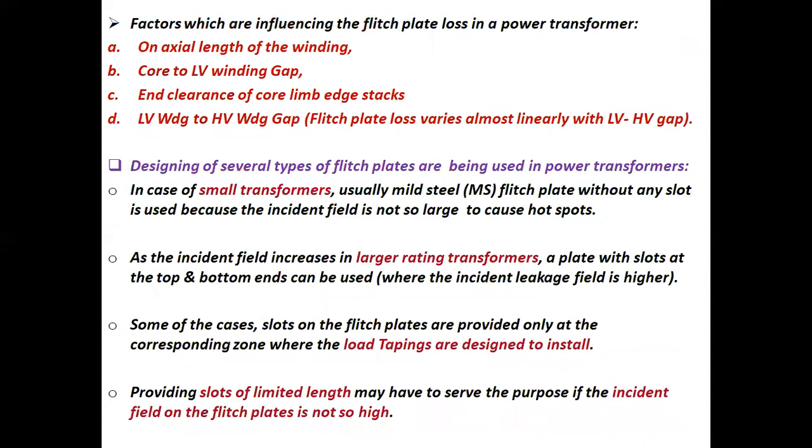Factors influencing the flitch plate loss in a power transformer: a. Axial length of winding. b. Core to low voltage winding gap. c. End clearance of core limb edge stacks. d. Low voltage winding to high voltage winding gap.